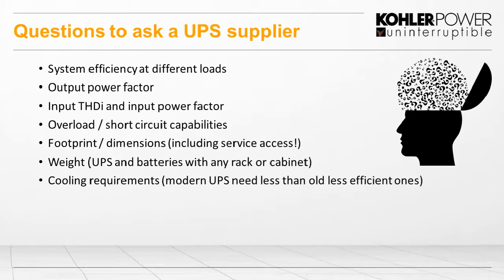The weight of the UPS and batteries, especially the batteries, can be extremely heavy, as we explained. So that would be a question to ask when you're planning your installation. Now, cooling requirements. The modern UPSs are much more efficient nowadays and need less cooling, but it must be considered. There are specifications, typically 40 degrees max for the UPS, but the cooling requirement for the battery is probably more critical. And as explained for lead acid, we need to keep it around 20 degrees.